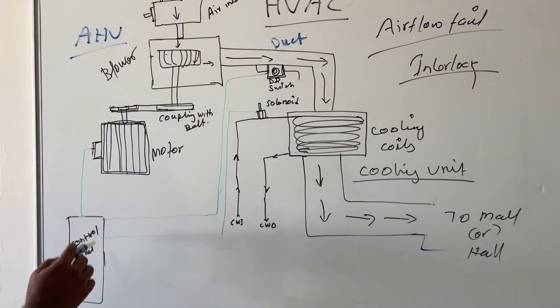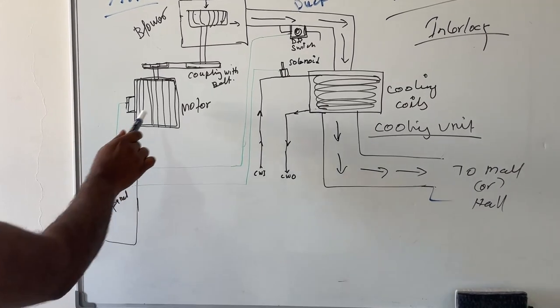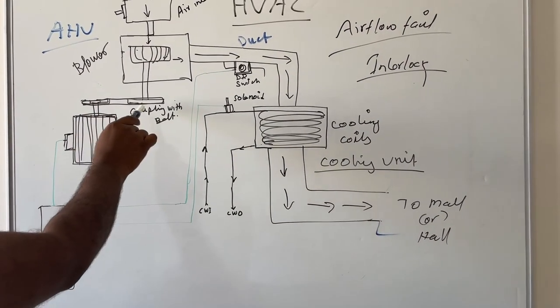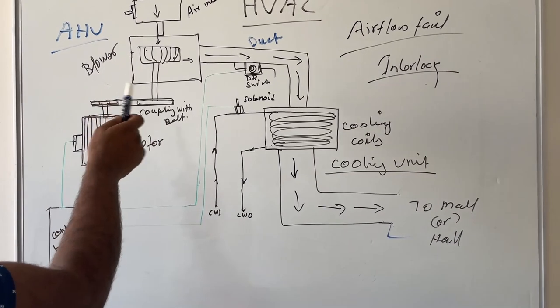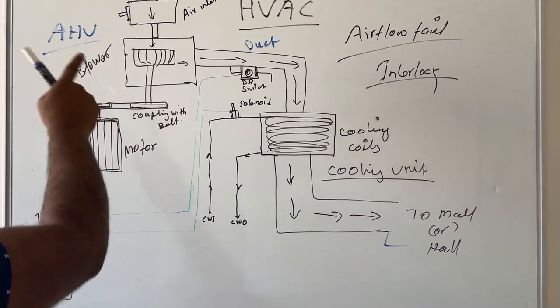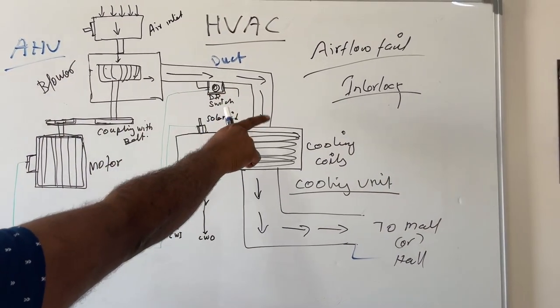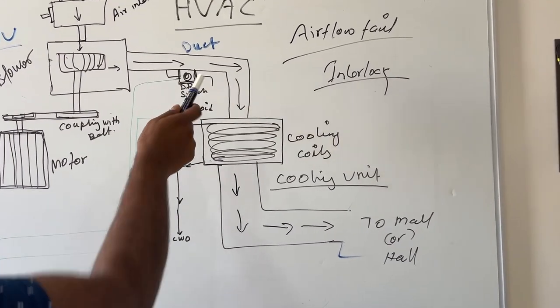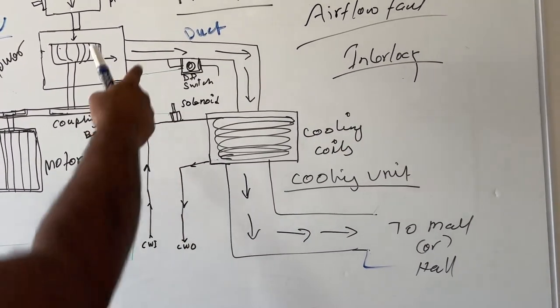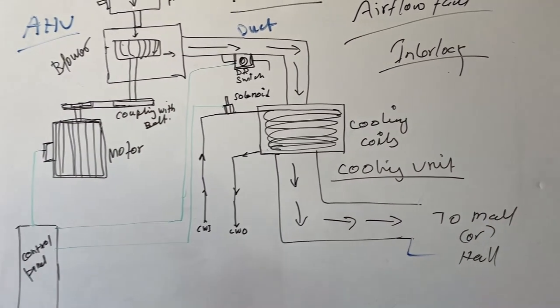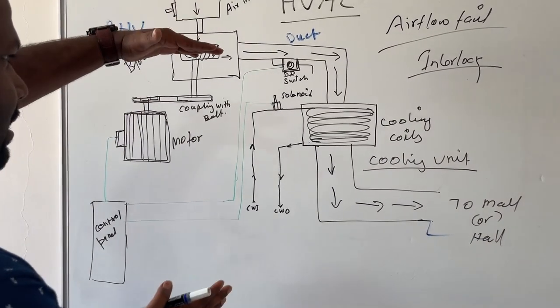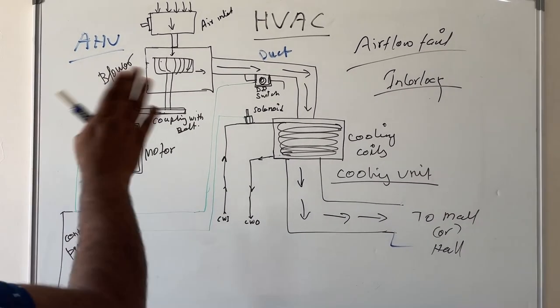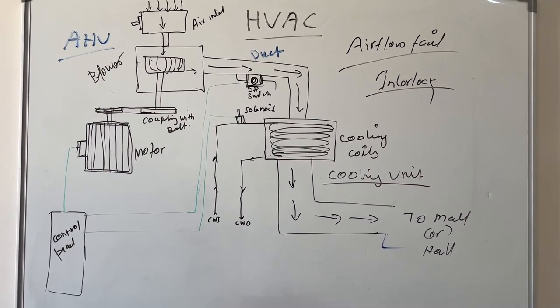Once this motor starts and the blower is rotating, due to the rotation there will be airflow through the duct. Through the duct, the DP switch will observe the small airflow through the micro switch, and it will give a signal to the control panel. By this system we will know that the blower is working and air is flowing through the cooling coils.